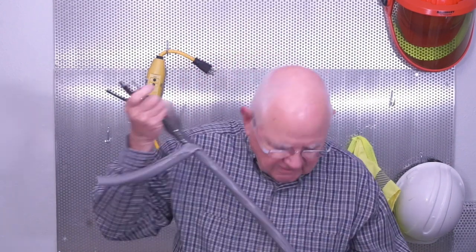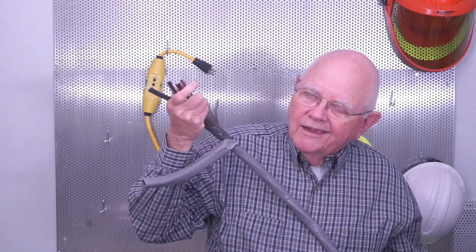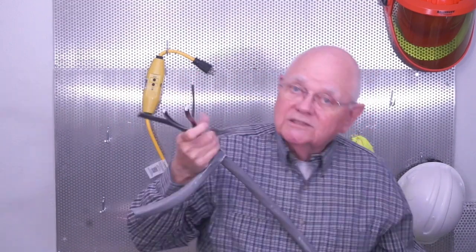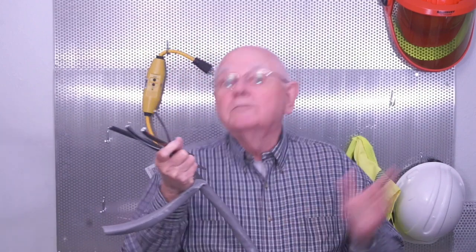Then the manufacturer on here also says something about SER after the SE. And that's okay. That's the manufacturer's information. The bottom line is it's Article 338 compliant type SE cable, so I can use it. I have my 3 conductors, which are insulated. These happen to be 2 AWG aluminum. So I could use this for a 100 amp service, couldn't I?